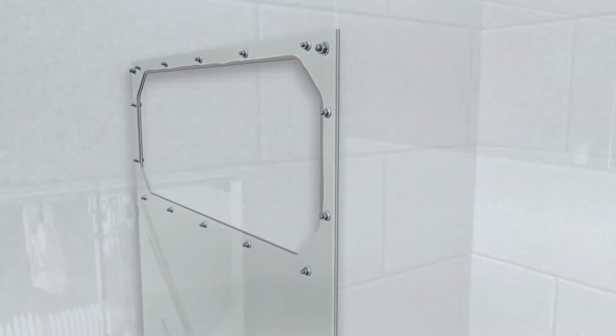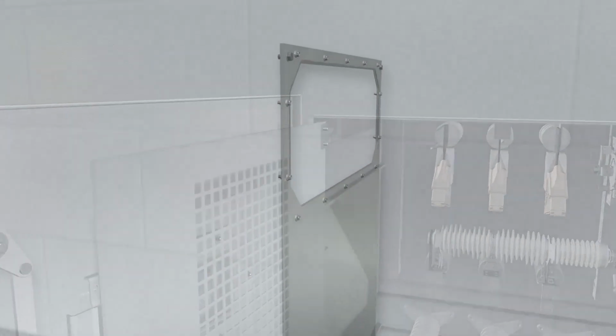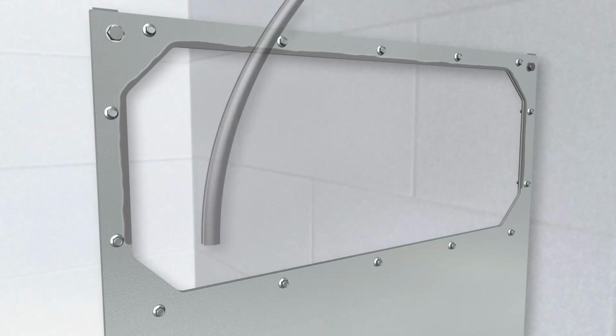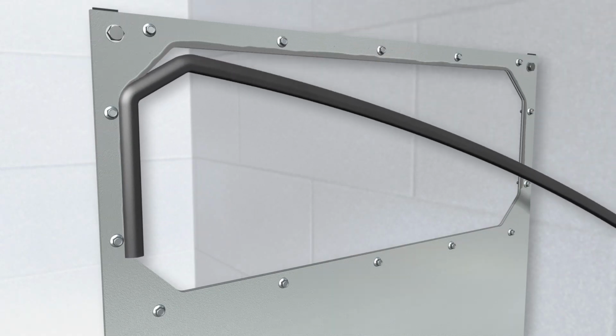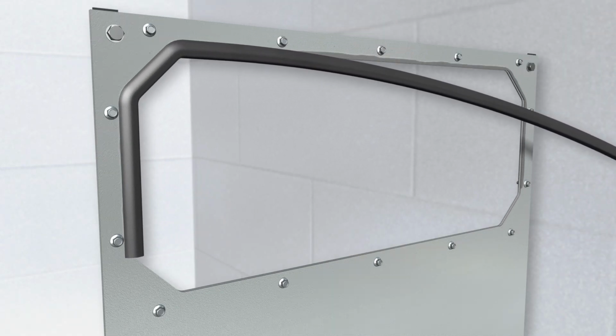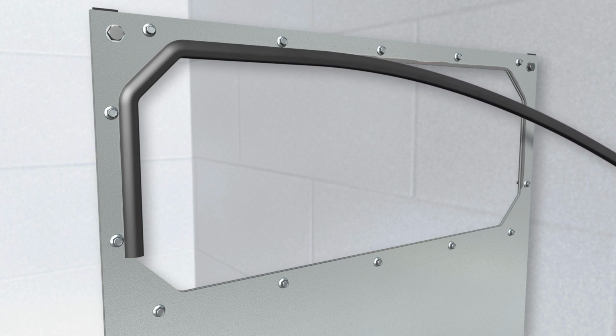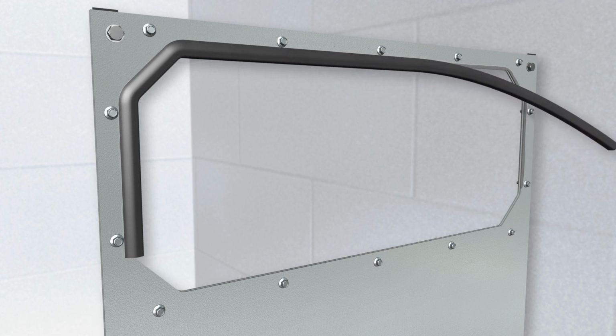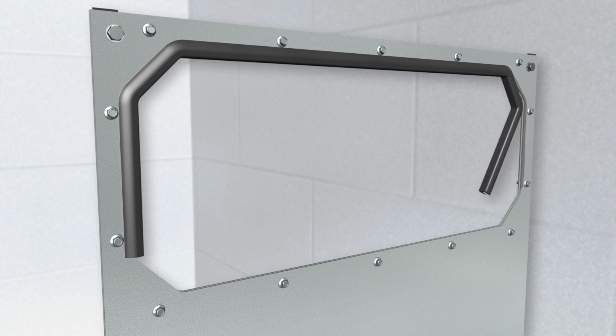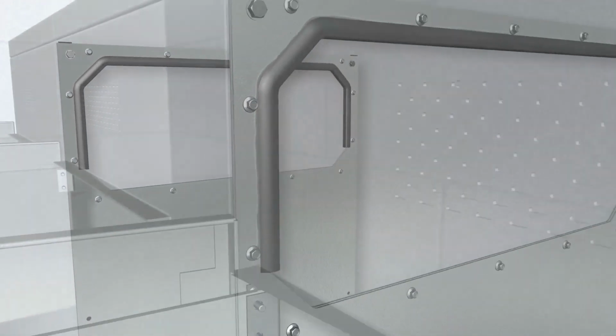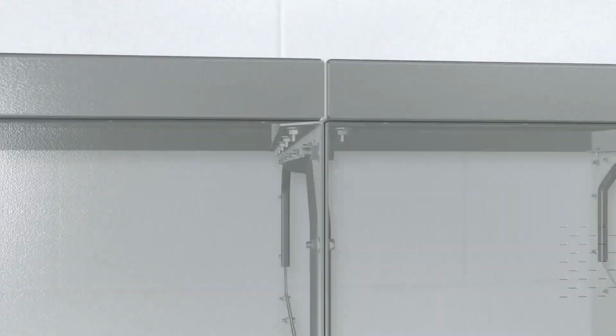After allowing the adhesive to become tacky, where it does not transfer to a knuckle when touched, start the channel gasket at the bottom front corner of the bus opening and, while verifying the gasket is seated completely over the opening flange, install the gasket at the front, top, and back of the bus opening.